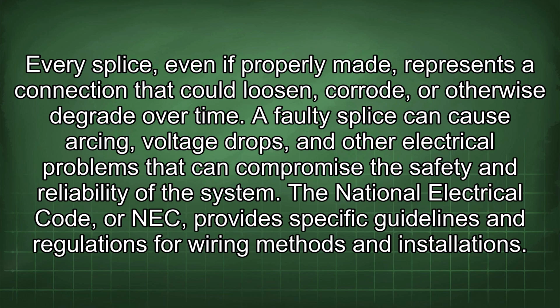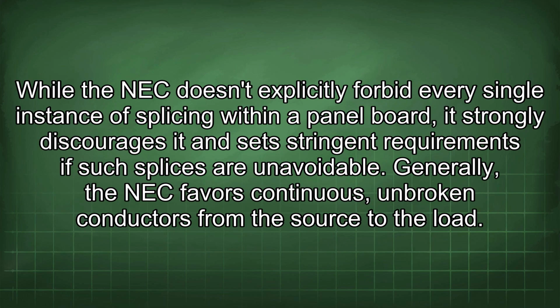the system. The National Electrical Code, or NEC, provides specific guidelines and regulations for wiring methods and installations. While the NEC doesn't explicitly forbid every single instance of splicing within a panel board, it strongly discourages it and sets stringent requirements if such splices are unavoidable. Generally, the NEC favors continuous, unbroken conductors from the source to the load.